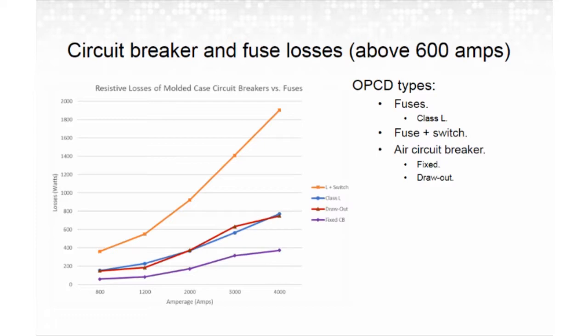And then at the bottom, a fixed circuit breaker is illustrated in purple, as it has the lowest losses of the group. When we look at this, it makes sense that a drawout circuit breaker would have higher losses because of how it contacts the bus with fingers instead of bolted connections.